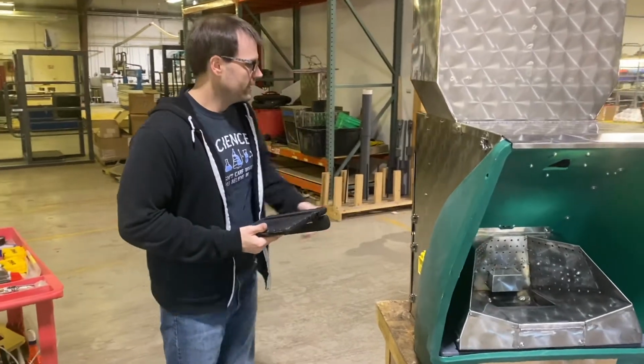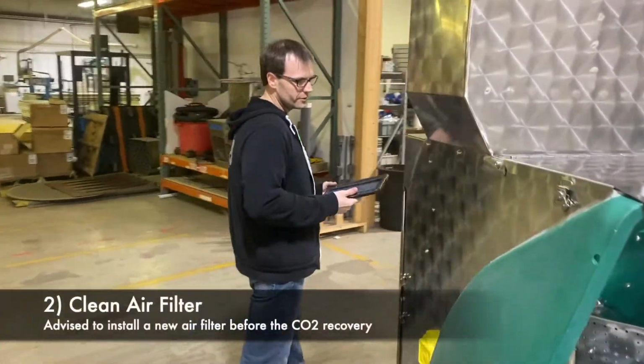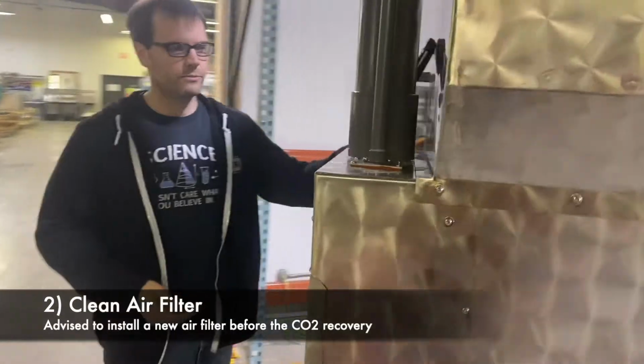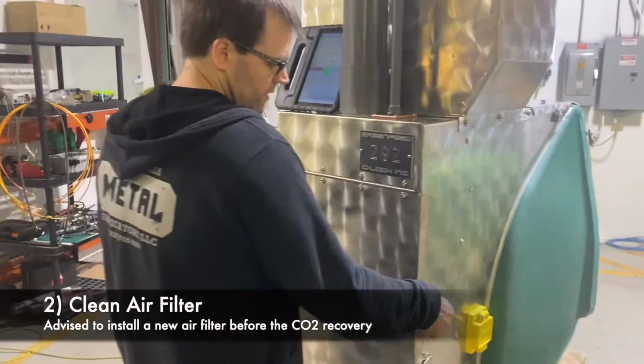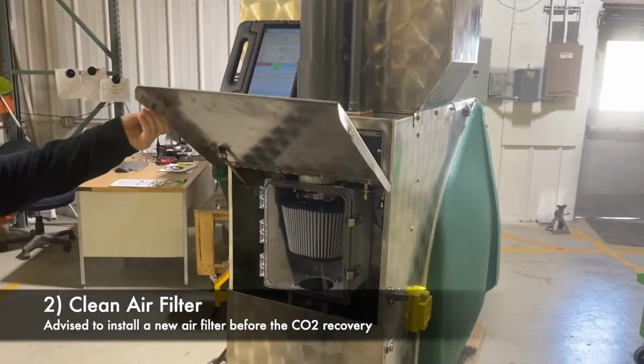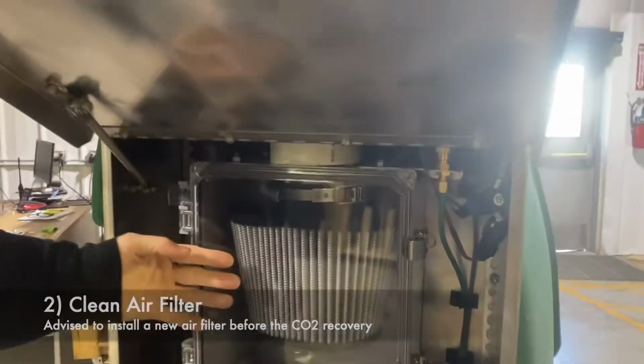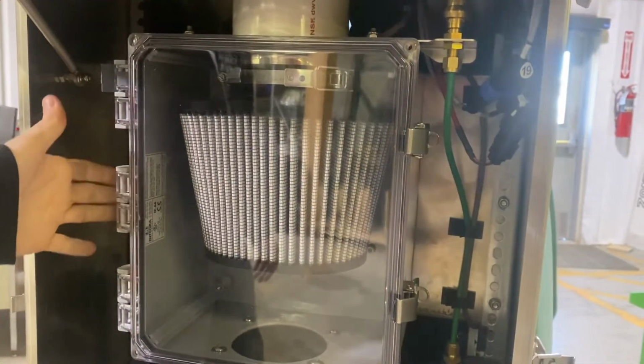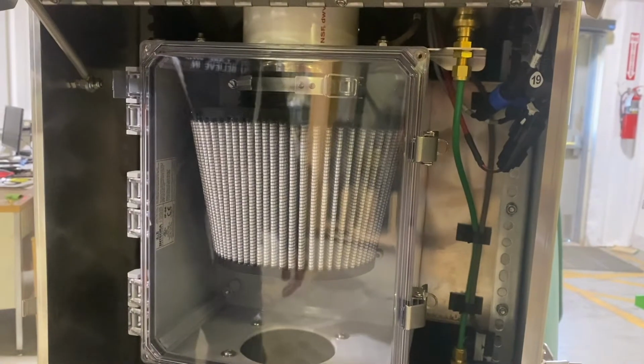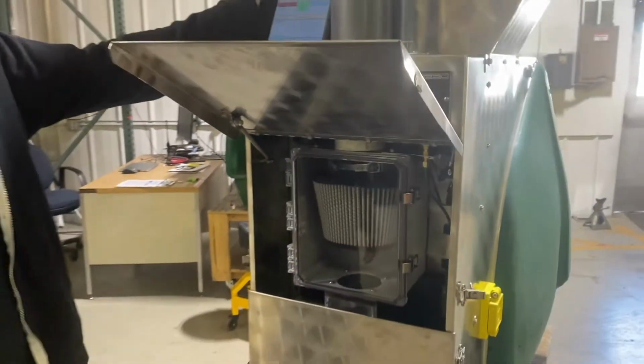The next thing, we want to make sure that we have a clean air filter. So if we come around back here and check our air filter, I would advise, even if you think it is clean, still clean it, replace it with a new one before you do a CO2 recovery device or release.